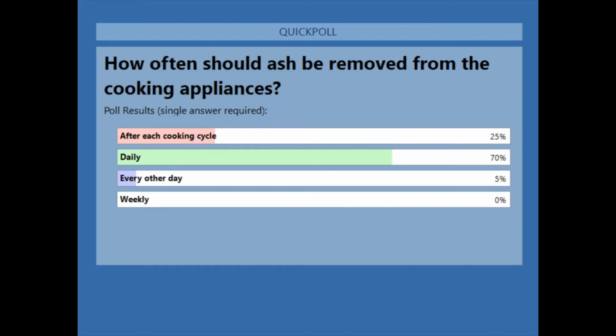Brian, what's your answer on that? Well, this is a little bit of a trick question because there's actually two correct answers. Both A, after each cooking cycle, and B, daily, are correct. This goes back to the owner's manual where it actually will specify for that. NFPA says a minimum of daily, but if the owner's manual states after each cooking cycle, that is what you would have to revert to. So you just got to check that manufacturer's manual and take a look at that.